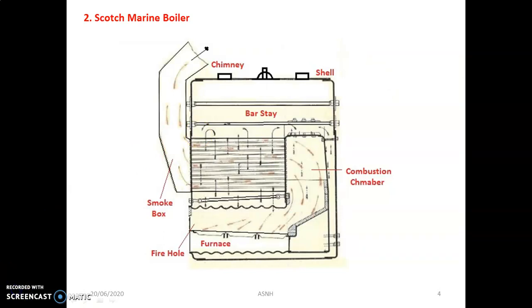The second important fire tube boiler is the Scotch marine boiler. Its main specialty is that it is probably the most popular boiler for applications in the range of 1000 kg per hour and pressure of around 18 to 20 bar. It is compact in size, occupies very less space compared to other boilers, and its construction is quite easy compared to other fire tube boilers.